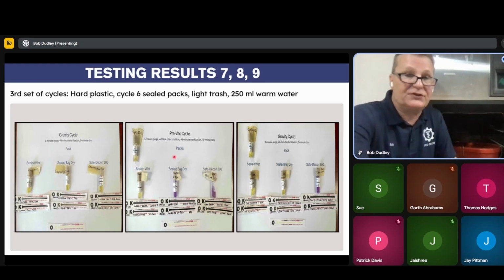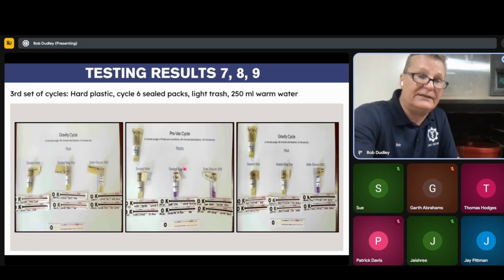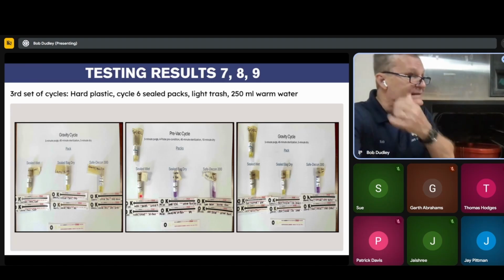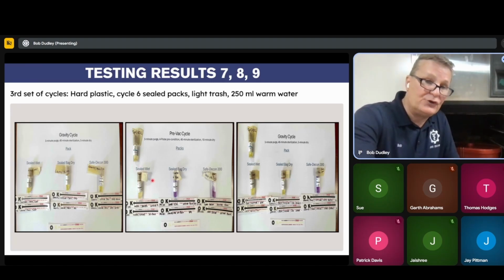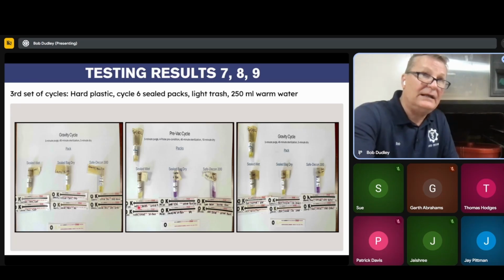So getting back here, this was the last of the tight packs that I did. I ran the pre-vac cycle with the sealed water. This bag didn't bust this time, and as you can see, it showed that we had steam. More than likely what happened is eventually that 100 milliliters of water inside that bag did heat up, and then once the cycle had completed and the pressure had dropped, that's why you're getting this false negative on these.